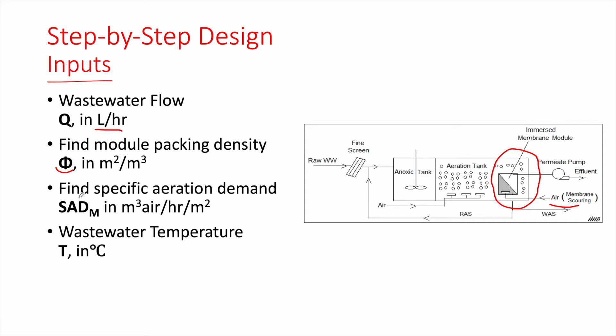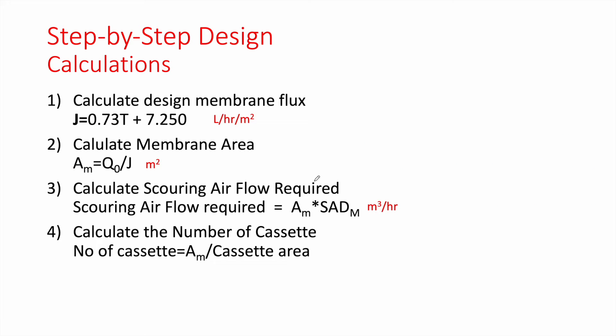Then we need the specific aeration demand SAD, which is typically 0.3 cubic meters of air per hour per square meter. Finally, we need the wastewater temperature T in degrees Celsius. With those inputs, we proceed to the step-by-step calculations.